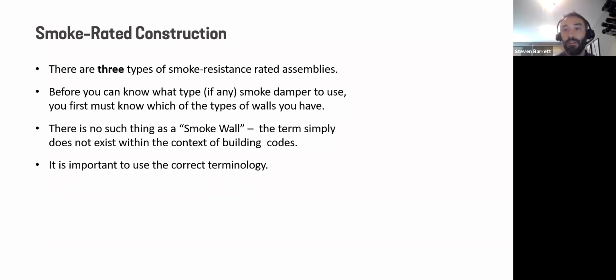So those were all of the fire rated assemblies. And if you remember, all of those, the result was provide a fire damper. The only exception was the shafts, where it was provide a combination fire and smoke damper. Now we'll get into smoke resistance rated assemblies and talk about their requirements of whether or not you need a smoke damper. And you'll see a little bit of difference here, how it went fire wall, fire barrier, fire partition. There is no smoke wall. That's not a term that's used in the code. It goes smoke barrier, smoke partition. And then we'll talk about a third kind of special type.